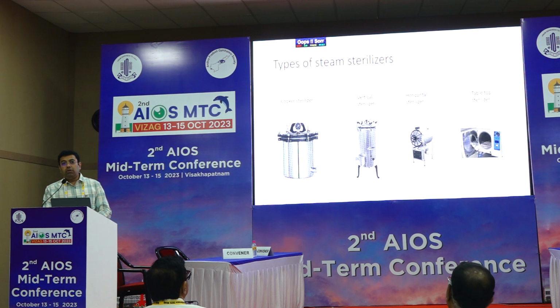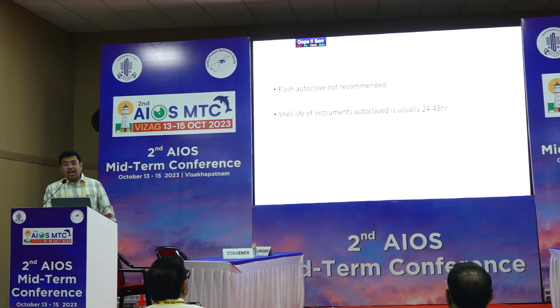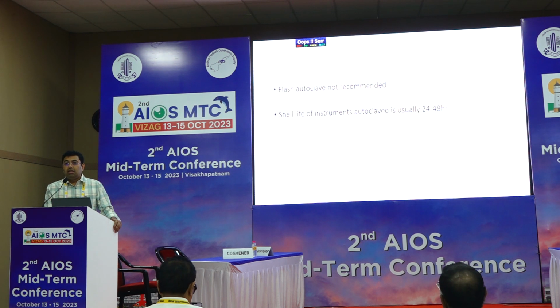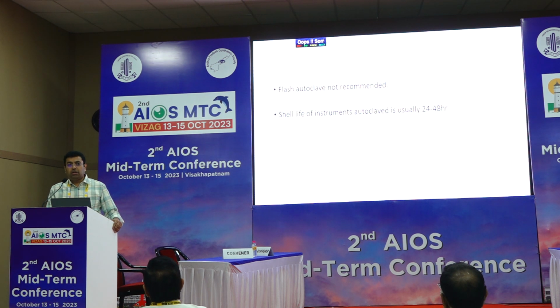The B class autoclave is very highly recommended. If you are doing phaco on a regular basis, then it is better to sterilize your phaco tubings in a B class autoclave. A flash autoclave is not recommended. We do not guarantee the sterility of instruments in a flash autoclave, because it is done for only about 7 or 8 minutes. If you still want to use it, you can use it on an emergency basis. Suppose something falls down from the table and you have no other alternative, then in cases of emergency, you can use a flash autoclave.